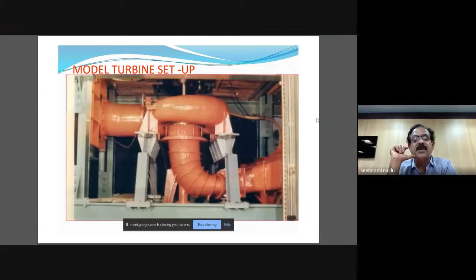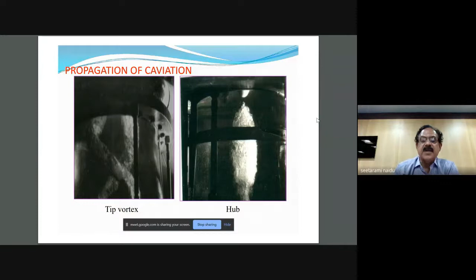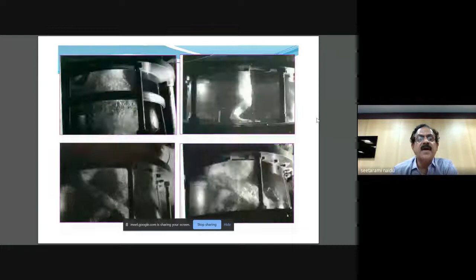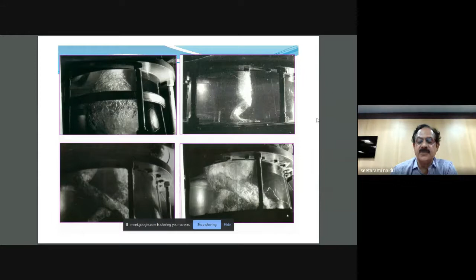This is one set showing the draft tube, turbine, etc. that was available at CWPRS for model tests. Here we can see Hub cavitation in Kaplan type turbines, and this is a Francis unit. You can see this helical, snake-like cavitation at the tip of the Francis turbine blades at higher discharge, and coconut-like Hub cavitation. These are actual photographs taken.